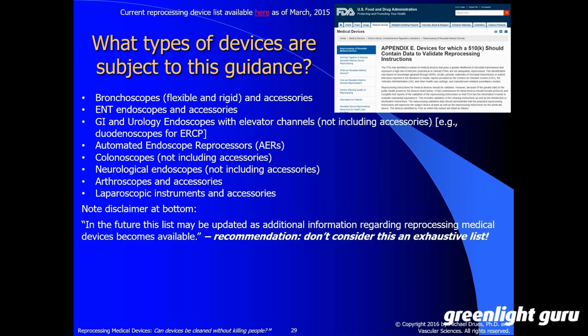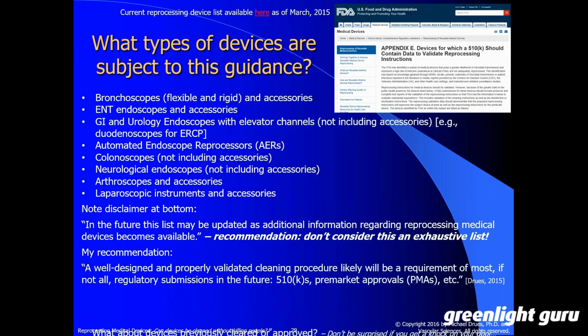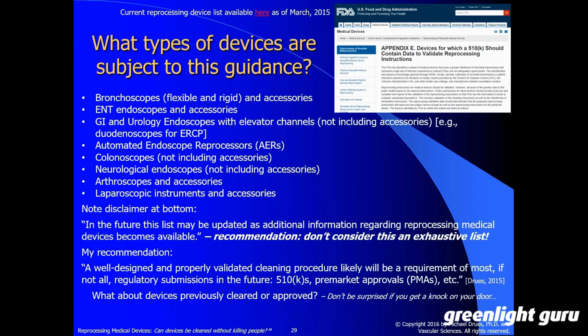people pay attention. But the bottom line is we have an obligation, never mind a regulatory obligation, we have an obligation as medical device professionals to do what needs to be done, whether it's required or not. And one last thing that I'll mention about reprocessing validations: I find it very unfortunate that some companies, even today, that are doing reprocessing validations are doing them in-house. But the problem with that is that those are not the people that are going to actually be reprocessing the device. So what good is doing a reprocessing validation if it's being done by the people in the medical device company, but it's going to be the people in the hospital that are doing the actual work? To me, that makes absolutely no sense, and yet, still to this day, people do that anyway.